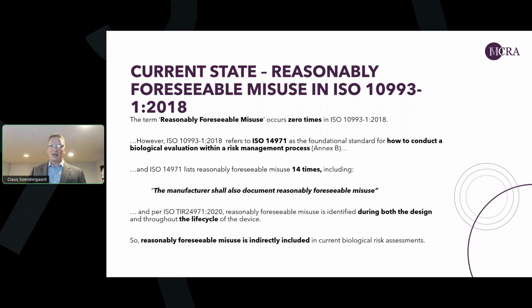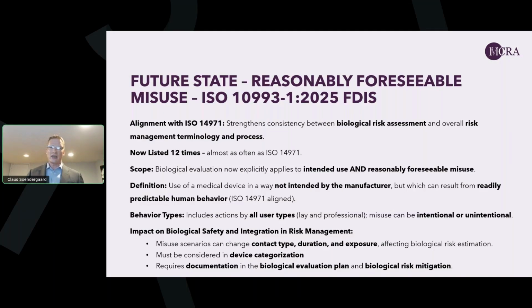So with that in mind, we could ask ourselves, is reasonable foreseeable misuse something that we should actually already now be looking at as part of our biological risk assessment, and is it a bit of a blind spot or a disconnect between those two standards? So this idea that there might be a little bit of a misalignment between 14971 and the focus there on reasonably foreseeable misuse, and the absence of that in the current revision of 10993-1, is probably one of the reasons why the upcoming revision that currently is in the final draft stage is now introducing the concept of reasonable foreseeable misuse as part of biological risk assessment as well.